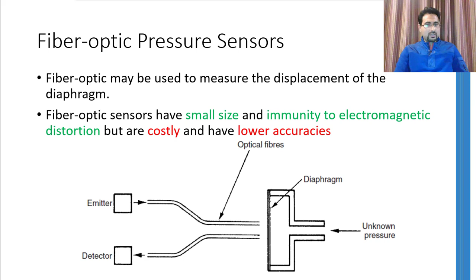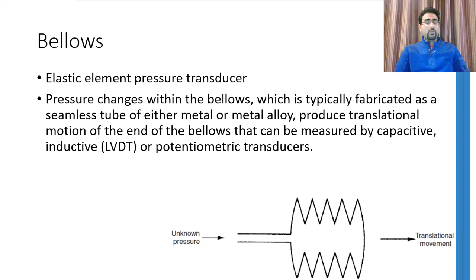By the use of multiple diaphragms, I mean that they are combined to make one big elastic diaphragm that will have multiple expansion points. These things are called bellows. And once again, the displacement may be measured using any suitable displacement sensing transducer. The advantage that we can get over here is the increase in sensitivity. However, bellows cost much more as compared to a simple diaphragm. And because of multiple joints, they are prone to failure as well.